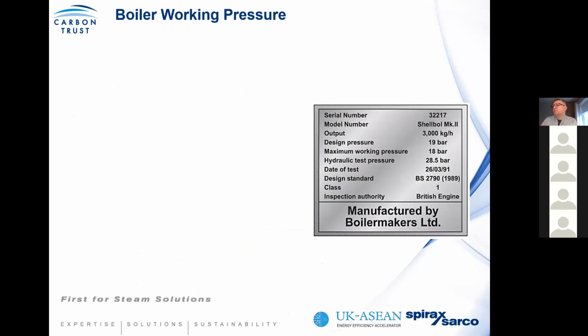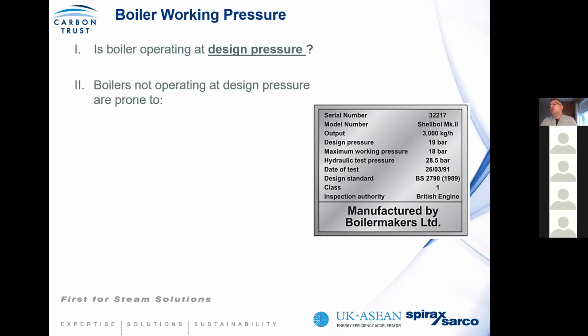two reasons. The working pressure will determine the quality of steam within the boiler, because what you're trying to do is, through addition of heat, create steam bubbles within the boiler water. At design pressure, the steam bubbles are very small. Below design pressure, these steam bubbles grow in size, which means that your water surface, or what we call your disengaging space in your boiler, becomes very turbulent once a boiler operates below its design pressure.